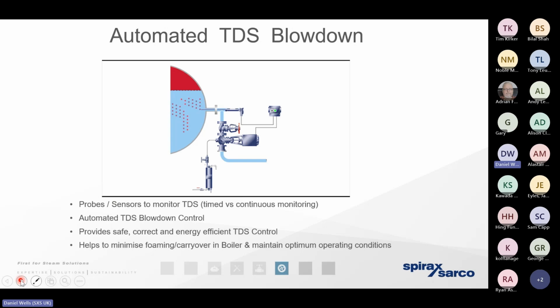Some of those chemicals and minerals are never going to solidify. They're always going to be held in suspension. But if that TDS level is allowed to rise to a high concentration, we're more likely to get foaming within the boiler itself. And with a fluctuation in boiler pressures, that foam can be drawn out of the boiler along with the steam, and that's really going to contribute to that wet, sticky steam that we're desperately trying to avoid. Not only is the steam going to have very little energy contained within it, but it also means that we're going to get more of the foam solidifying and changing state to scale. That scale can result in quite a bit of erosion of sensitive ancillaries, but that scale can also bind itself to heat transfer surface areas, meaning we've got a further barrier to heat exchange and a further inefficiency.